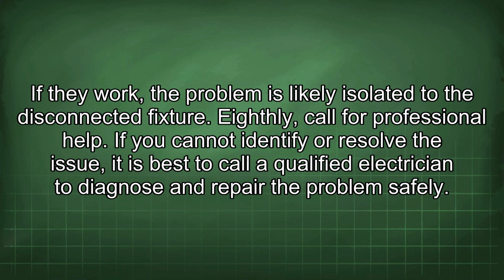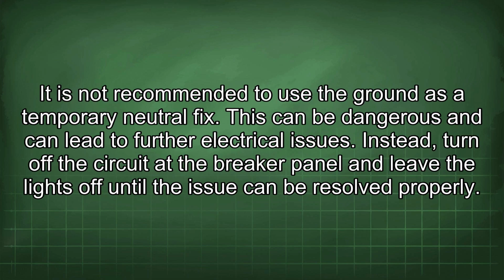Eighthly, call for professional help. If you cannot identify or resolve the issue, it is best to call a qualified electrician to diagnose and repair the problem safely. It is not recommended to use the ground as a temporary neutral fix. This can be dangerous and can lead to further electrical issues. Instead, turn off the circuit at the breaker panel and leave the lights off until the issue can be resolved properly.